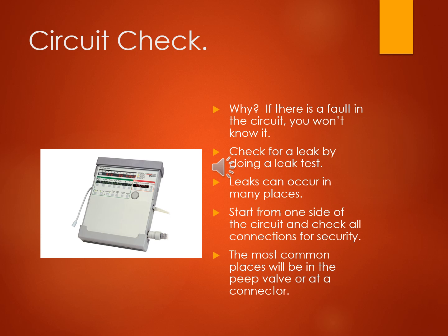If you backspin those before you put them on, it has this positive pressure keeping that circuit tight, and you want those things to be tight on there because you're going to flip that ventilator back and forth when you're moving a patient either outside the hospital or going to CT, MRI, when X-ray comes in. Whatever you're doing, you want to make sure that they stay nice and snug.